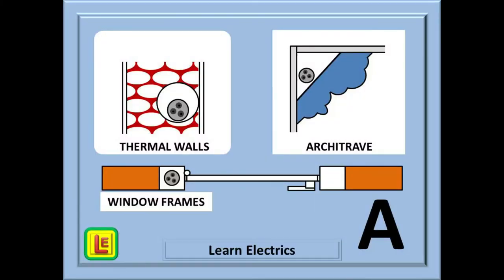Reference method A is where the cables are generally enclosed in building materials, such as insulating walls, window frames, and architraves. And it is the architrave that is the key to remembering method A. Architrave begins with the letter A. A is for architrave and other building materials. It's easy.